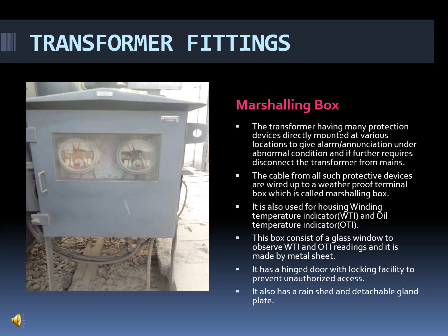This box consists of a glass, as shown in the image, to observe the WTI and OTI readings, and it is made of metal sheet. The advantage of the marshalling box is that it has a hinged door with a locking facility to prevent unauthorized access. Only an authorized person can access this door by having a locking facility. See, at the top side of the marshalling box, it has a rain shade and a detachable gland plate, and below that of the marshalling box.